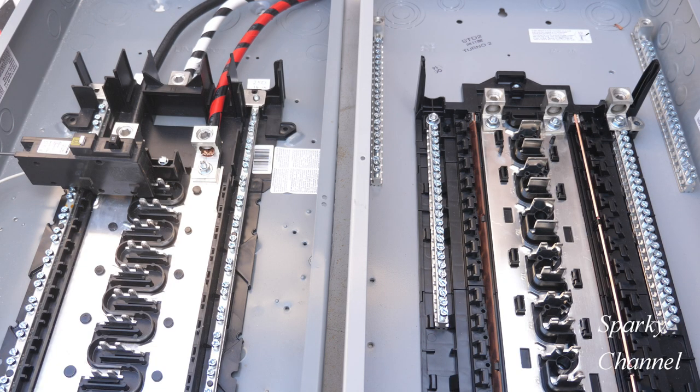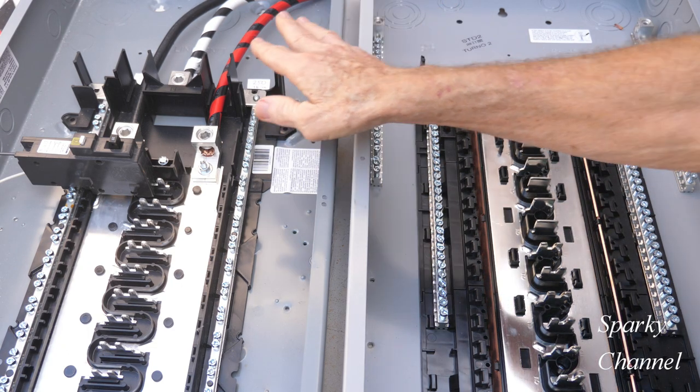There's only one instance where you want to bond together your equipment grounding conductor and the neutral bar — that is when your panel is the first means of disconnect. These are convertible panels, both of these.